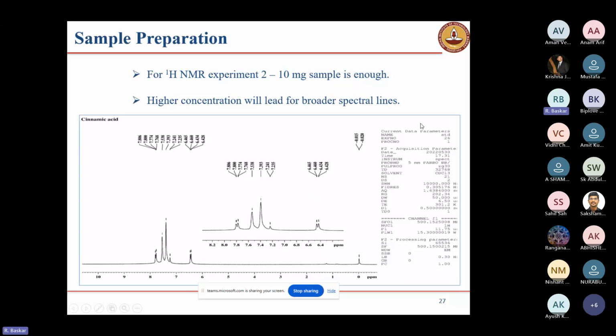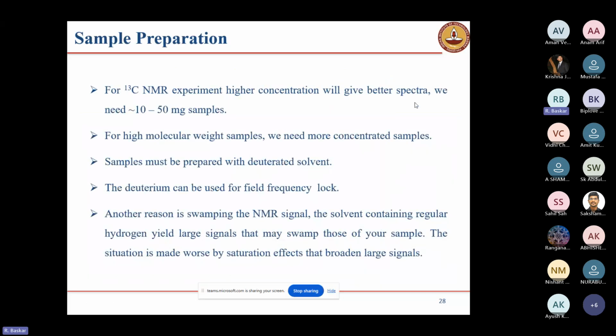A higher concentration will lead to line broadening. Next, for C13 NMR, we need a higher concentration. Shimming will not affect C13 experiments as much. For high molecular weight samples, we need a more concentrated sample. The sample must be prepared with deuterated solvents. The deuterium can be used for field locking. Locking and all, I will tell you later when I explain the working principle. At that time I will explain what locking is and what shimming is.